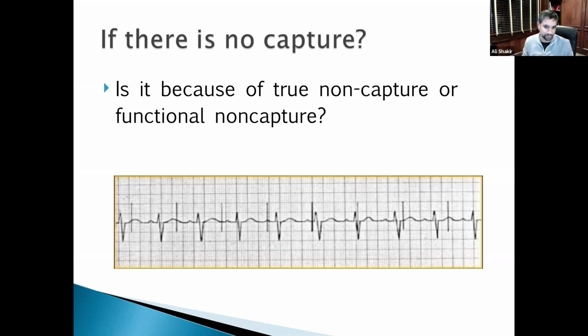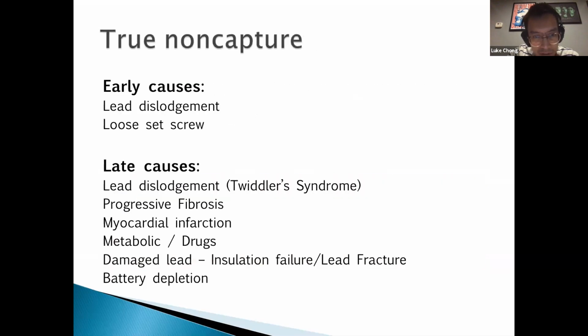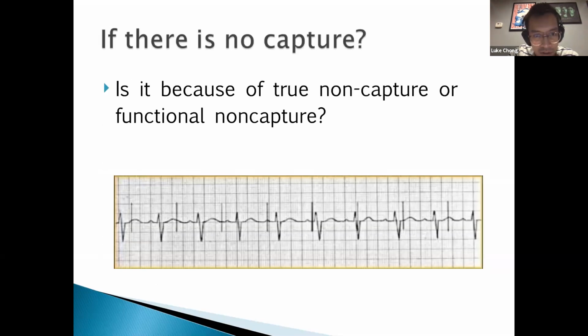So with regard to non-capture, looking at this strip, what stands out to me is that the first two pace complexes fall within the duration of the T wave during a period when you would expect the ventricle to be refractory. So I would say that corresponds to functional non-capture in that circumstance. Some of the other pacing spikes fall at phases where you might reasonably expect capture to occur. So I think the third one, that to me represents true non-capture. As to the subsequent ones, I will say actually 4, 5, and 6 occur at phases where you're already seeing intrinsic conduction go through.